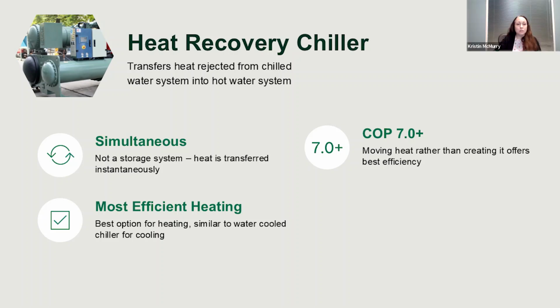That simultaneous piece is pretty crucial and can sometimes be hard to understand. For example, in a climate like Minnesota, the heat recovery chiller may not be the best fit because in summer we're adding cooling since the weather is hot, but if we aren't always running cooling, like in winter, we have no byproduct heat to recover and use elsewhere.